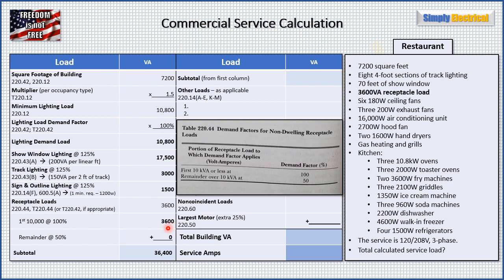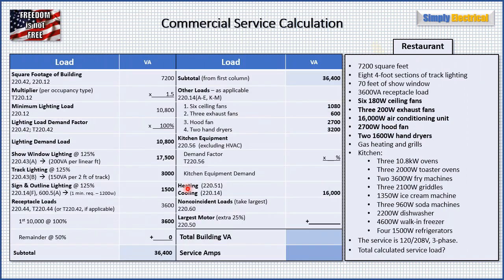Now that we have all those values — the lighting demand load, show window, track, sign and outline lighting, and receptacle loads after demand factor — we add them up. The total we come up with is 36,400 VA. We slide that number right up to the top of the next column: 36,400.